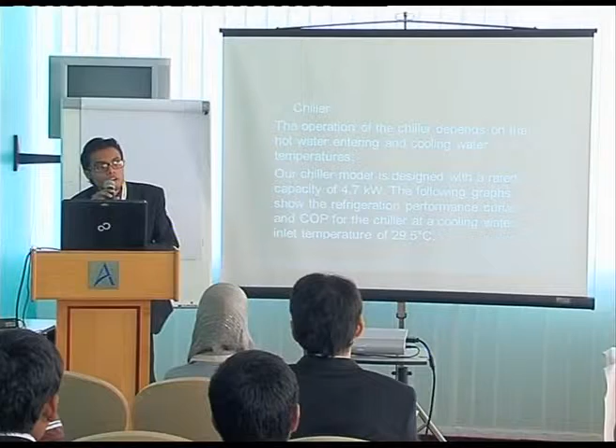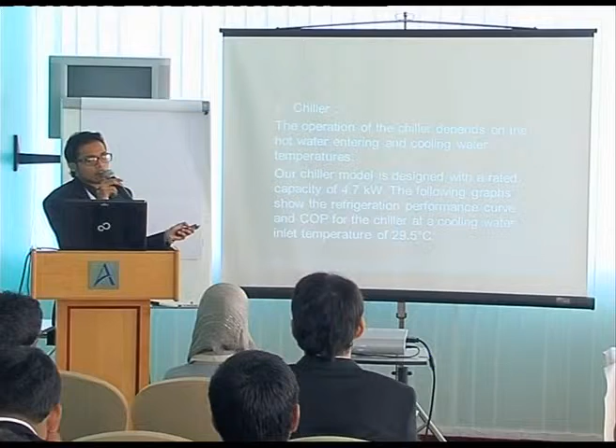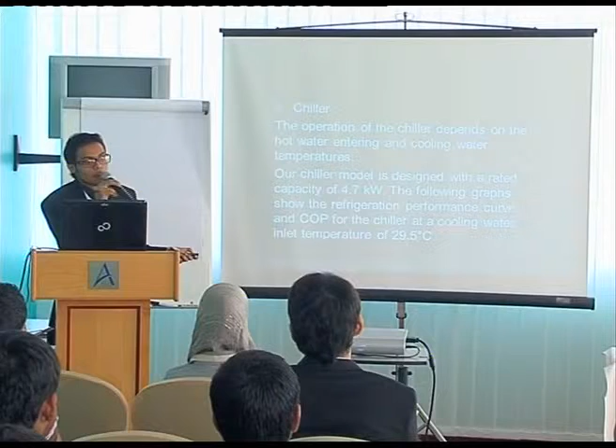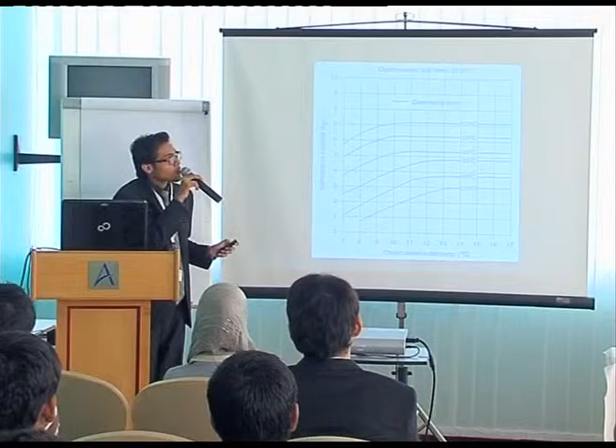Now, the chiller which we have considered here is a standard 4.7 kilowatt chiller, and the inlet temperature of the cooling water is 29.5 degrees centigrade. Now we have a standard graph, with the chilled water outlet temperature on the x-axis and the refrigeration capacity of the chiller on the y-axis, keeping in mind that the cooling water inlet temperature assumed here is 29.5 degrees centigrade.